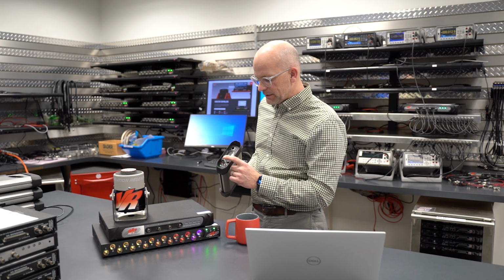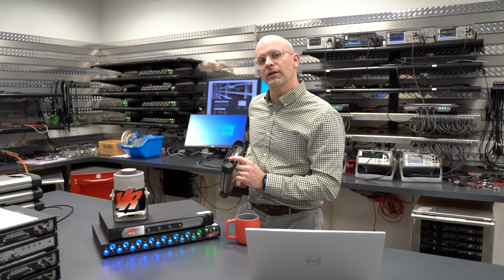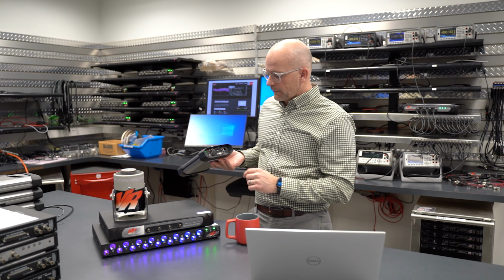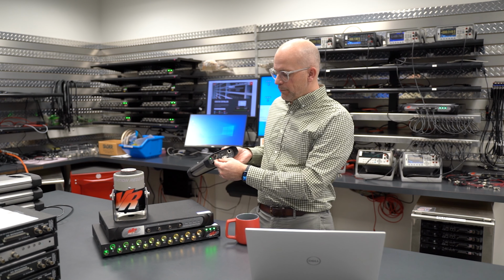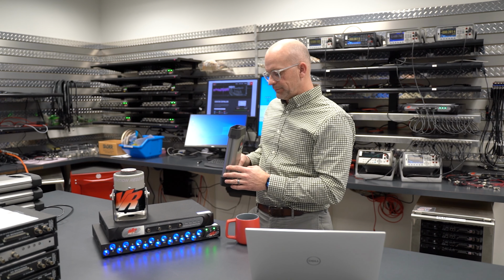The back also has an output, so you can use this for modal type testing. You can also use this for connecting to Vibration View, so you can actually use this device as a controller as well. So just like the 95 and the 10500 we'll talk about in a minute, this can also be used as a shaker controller. And then it also has power for charging the internal battery, as well as power for using external batteries, so you can hot swap those as well.